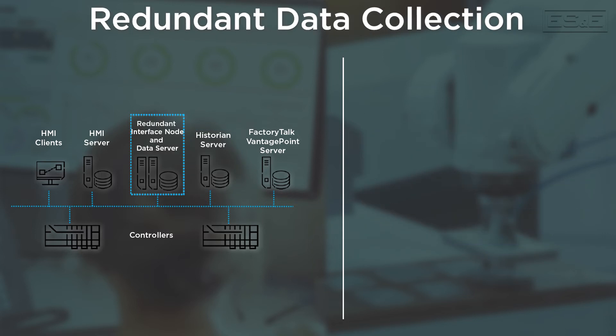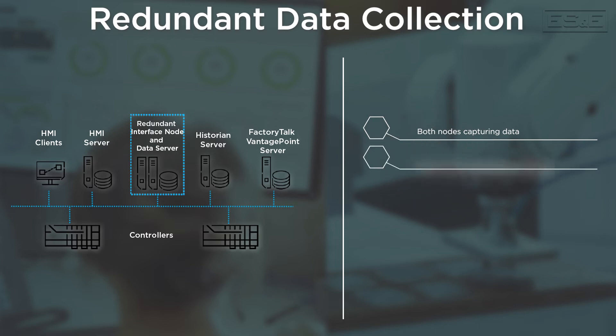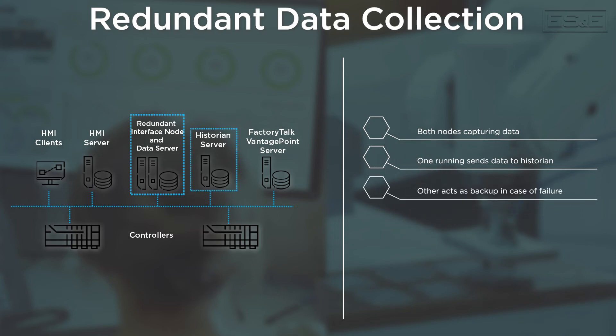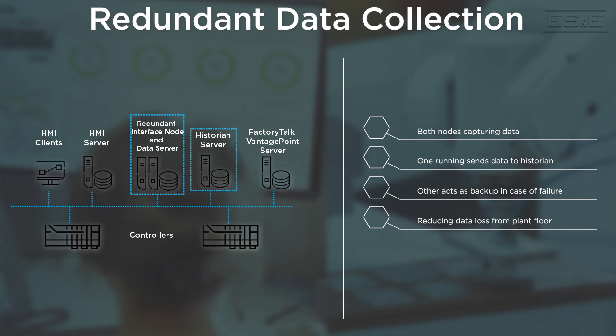We can take that a step further and make those interface nodes redundant. Both interface nodes are capturing data from the controller, and the one that is available and up and running is the one actually communicating data to the historian. If that interface node fails, the other one immediately picks up and takes over sending data to the historian, thereby reducing or eliminating data loss from the plant floor. When you're talking about digital transformation, this data will grow to become invaluable — it creates great disruptions without it. As you progress down your digital transformation journey, this is something you have to think about long term. Historian SE helps address that with redundant interface nodes.